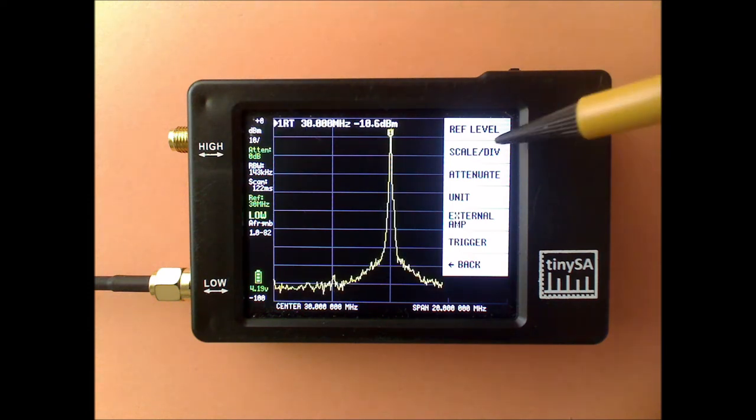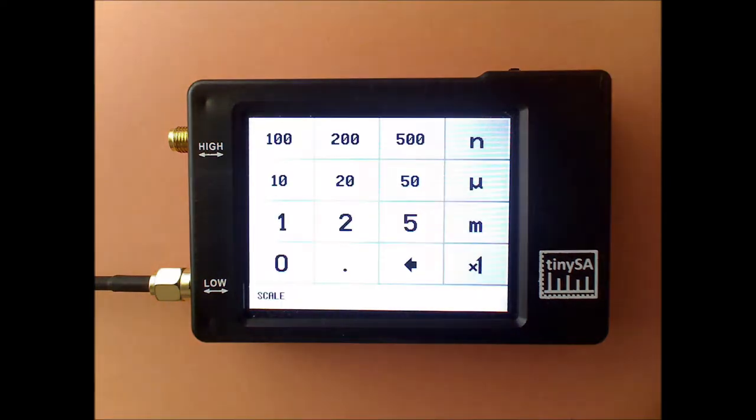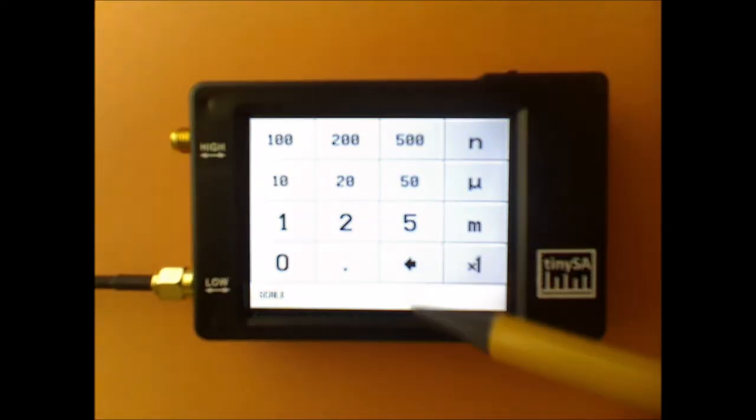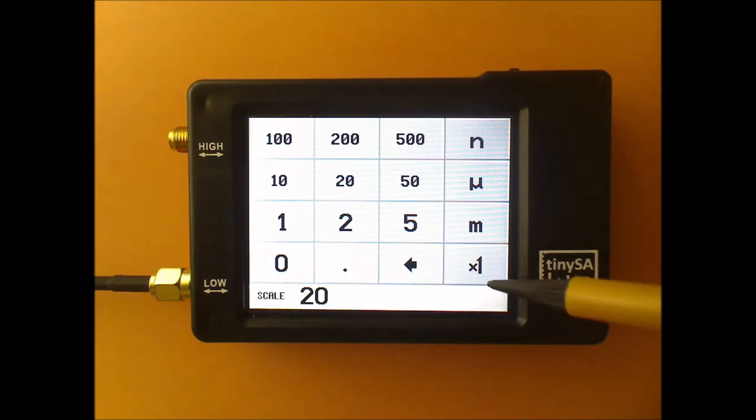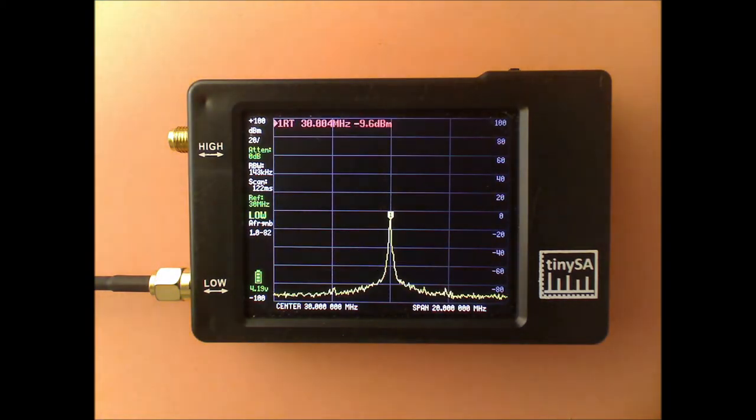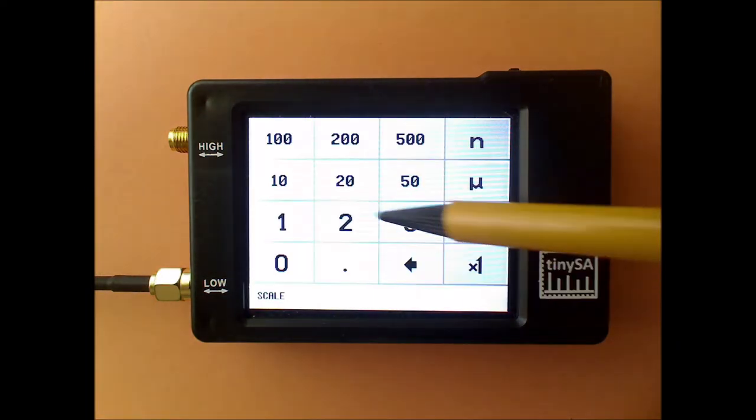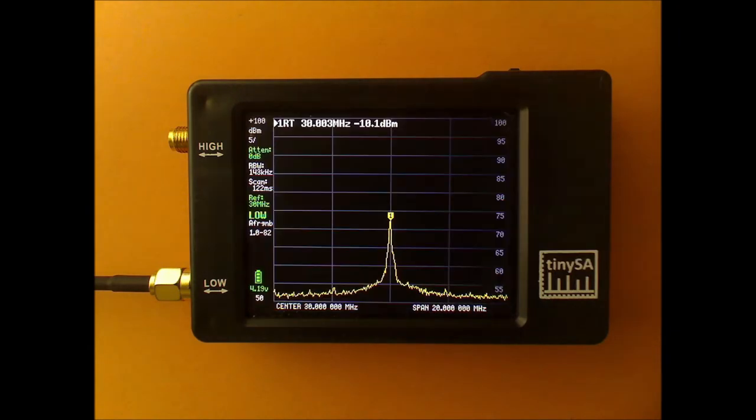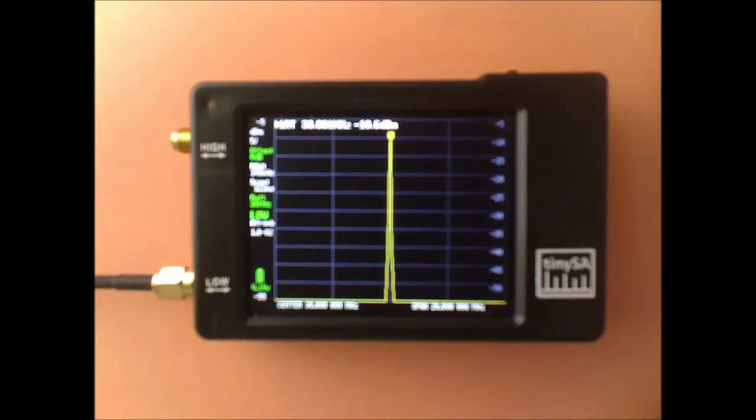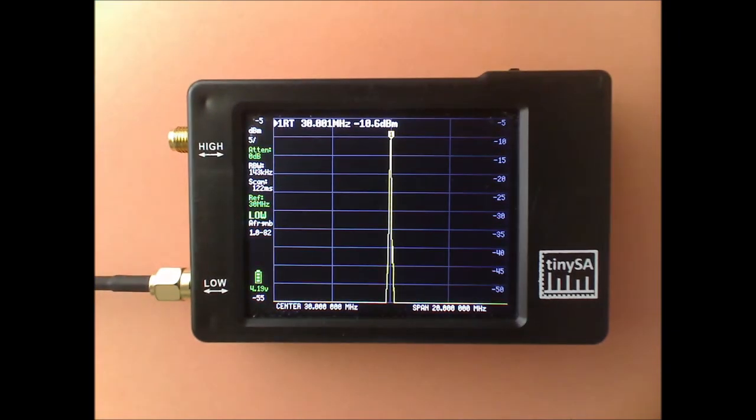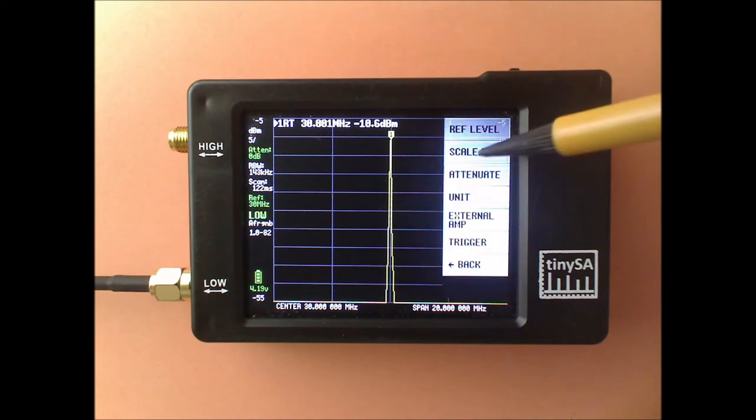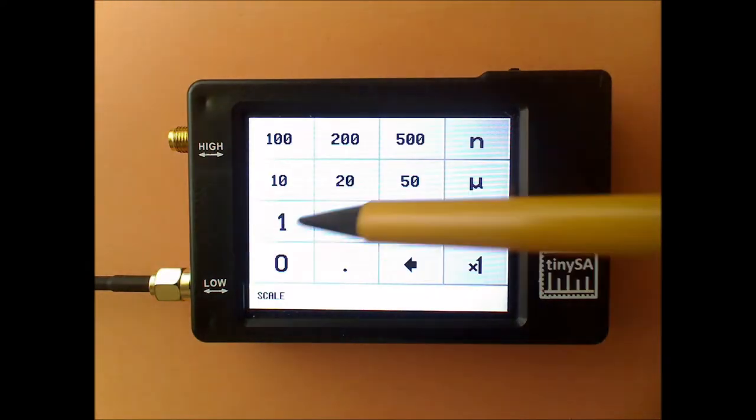But if necessary you can set it to a different value, for instance if you have strong signals you can go for 20. But if you want to see a lot of detail then you can also set it to 5, and back again to 10.